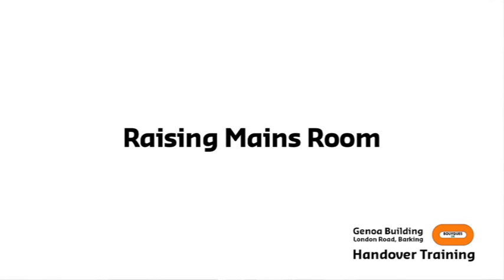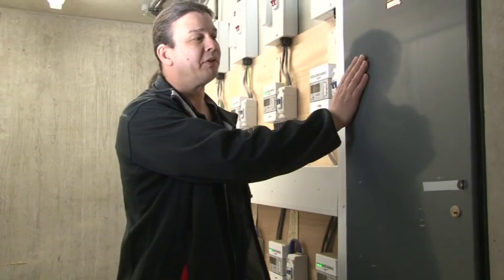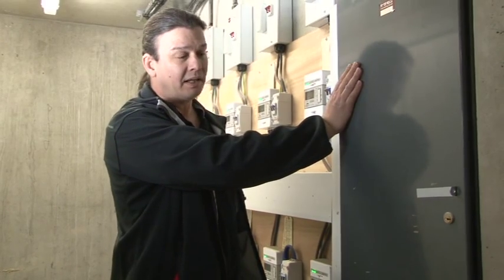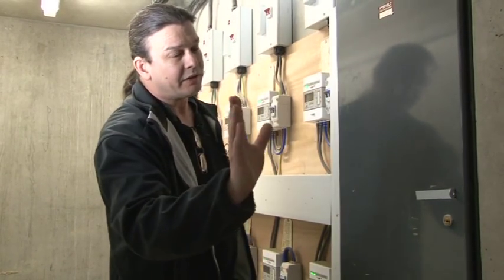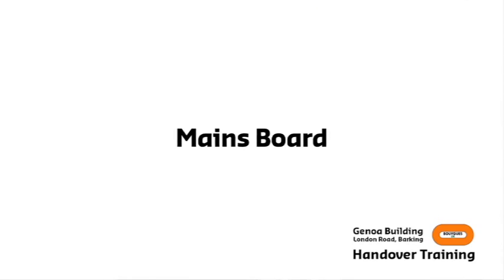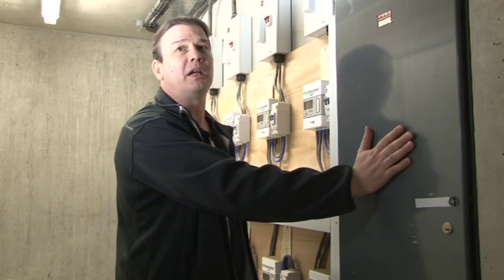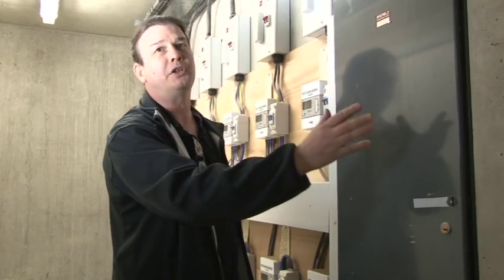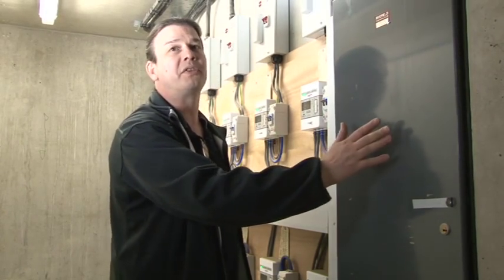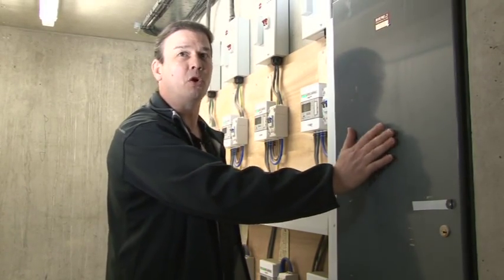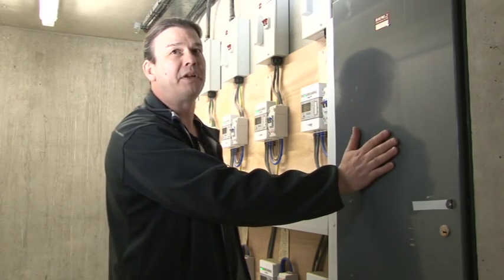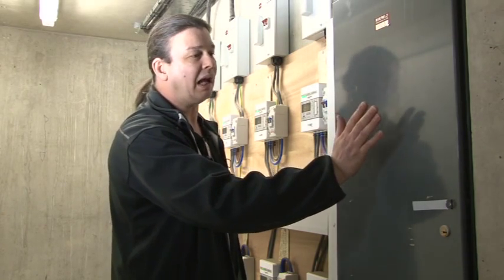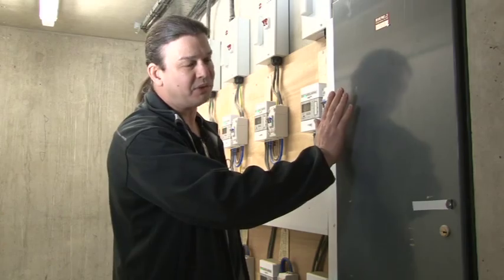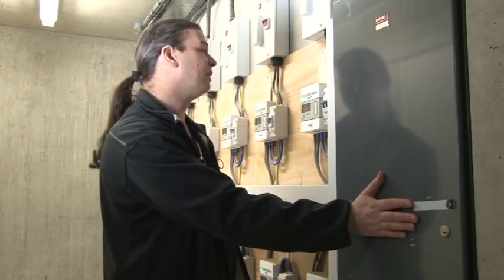Okay, each floor is fed from a rising main. The rising main comes up from the main LV as we looked at earlier. This board has no user interface. It is purely for access by UK Power Networks, one of the network providers, not the meter providers, network providers. This is the way that they demand that the systems are set out.